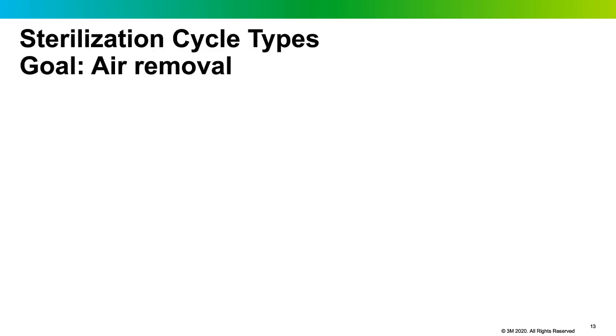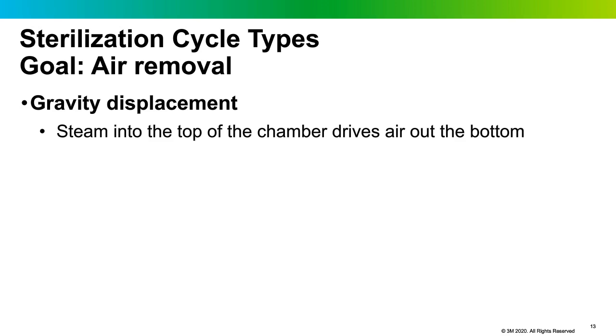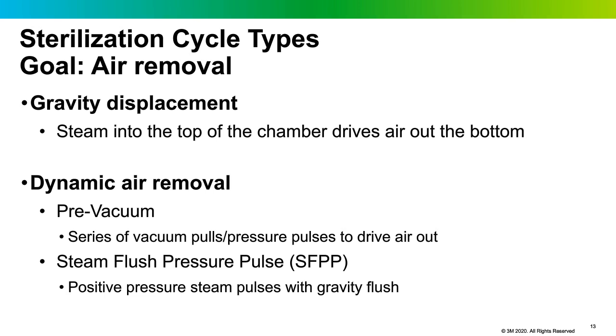All methods of steam sterilization have a way to remove air from the chamber and load items during the conditioning phase. Sterilizers may have multiple types of air removal. In a gravity cycle, steam is pumped into the top of the chamber, driving air out through the drain. Dynamic air removal is an umbrella term that includes pre-vacuum sterilizers — where a series of vacuum pulls and pressure pulses very effectively remove air — and steam flush pressure pulse chambers, which use positive steam pulses and gravity flushes but never pull below atmospheric pressure.